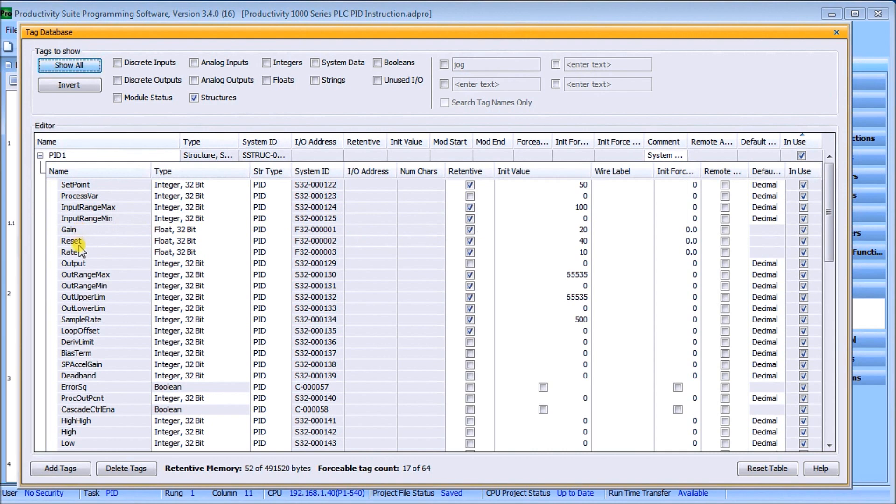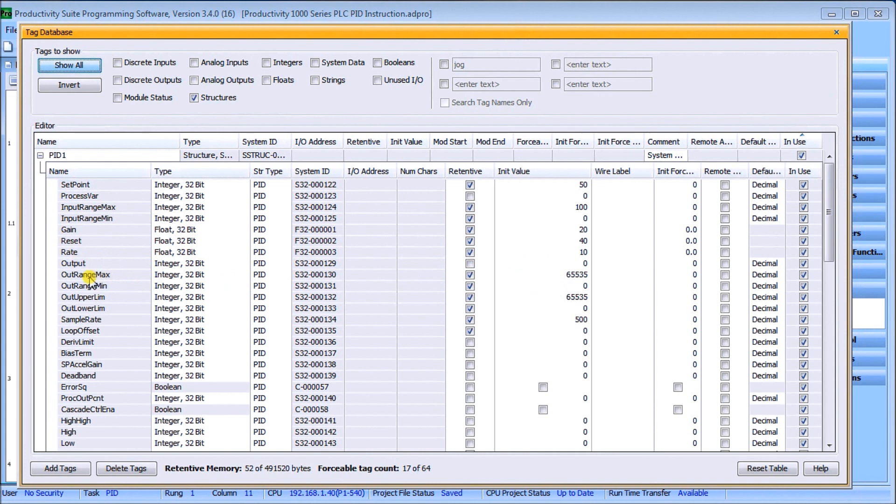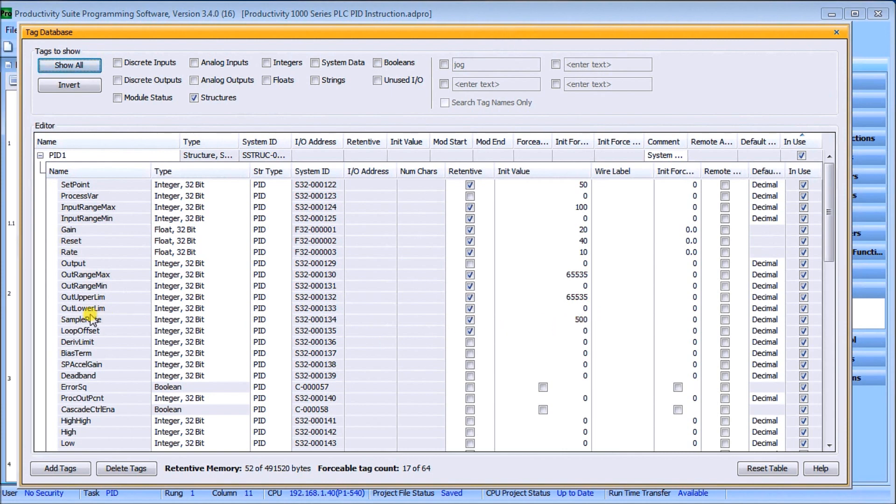Then what I have is my gain, my reset, and my rate, which is my P, I, and D. What I've done is I've changed them to floating point 32-bit. That means that my variables when they get auto-tuned can now be a decimal point, which is very important and seems to be better control. Then I have my output, which is going to be integer 32. Then I have output range max and min, which again I set for my zero to 65535. Then I have my output upper limit and lower limit, which must be also set from zero to 65535. Our sample rate is set for 500, which represents 500 milliseconds, which is two times a second that I've asked this to do the calculation for my PID.